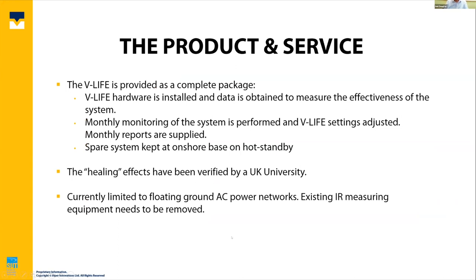So we install the hardware. We obtain data from the hardware, we modify the algorithms as a result of that hardware, and then we monitor the performance of the system on a monthly basis, and then modify the V-Life settings as necessary. So the hardware associated with providing this service is embedded in the V-Life. And then we have some special software running, which activates it and then modifies the algorithms on a dynamic basis.